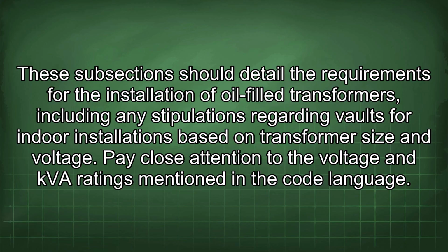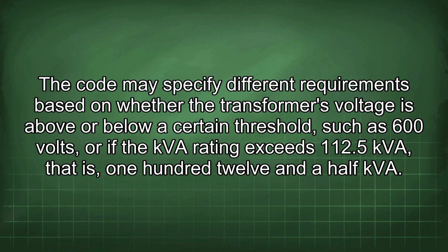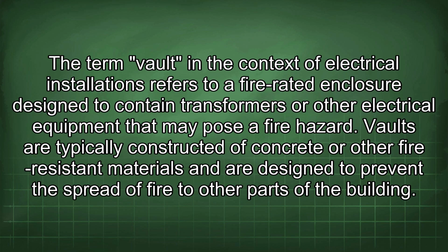Pay close attention to the voltage and kVA ratings mentioned in the code language. The code may specify different requirements based on whether the transformer's voltage is above or below a certain threshold, such as 600 volts, or if the kVA rating exceeds 112.5 kVA. The term vault in the context of electrical installations refers to a fire-rated enclosure designed to contain transformers or other electrical equipment that may pose a fire hazard.